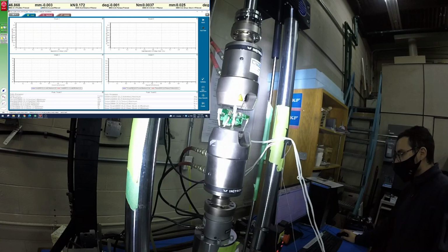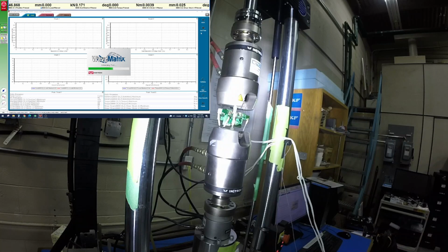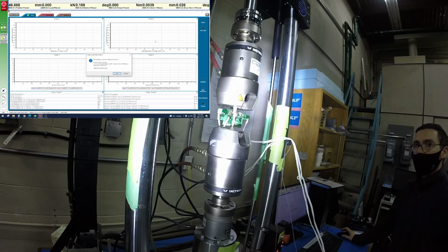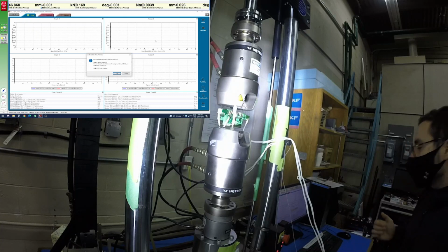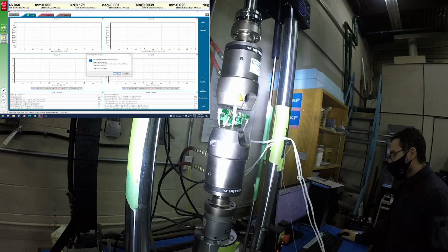And then what we want to do, we can click Start here, and the test will initialize. We want to make sure, once again, obviously, that we're watching the test and making sure that we're ready to adjust any limits if something gets tripped. So we can click OK to start running the test.